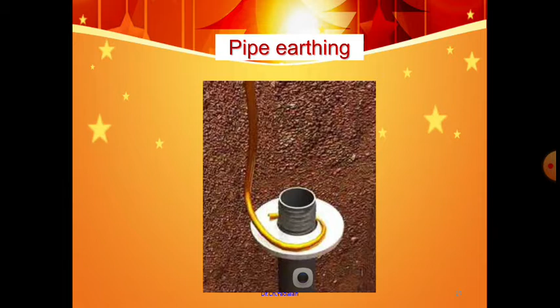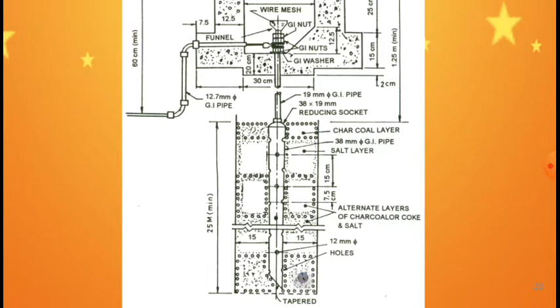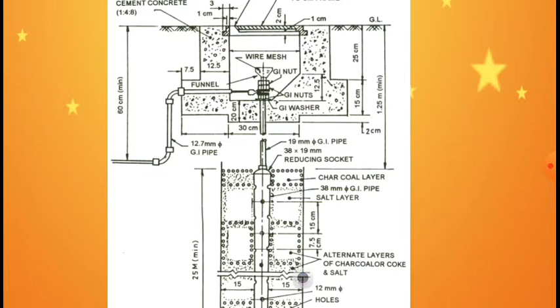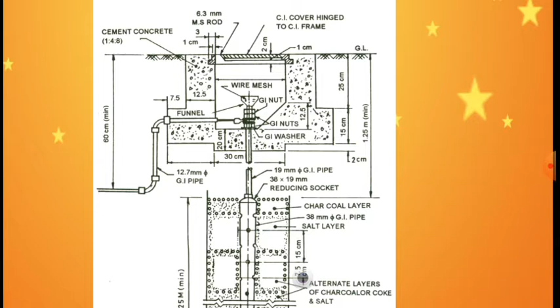So what it contains here, if you are observing, is a GI pipe of 38 mm dia, 2.5 m long, placed vertically in a pit. The pit is nearly 2 to 3 meters. The pipe is tapered at the lower end for easy driving into the soil. You can see the bottom tapered. The pipe is surrounded by pieces of coke or coal and salt in alternate layers of thickness 15 centimeters. Another pipe of 19 mm dia, 1.525 meters length, is connected to the 38 mm pipe.